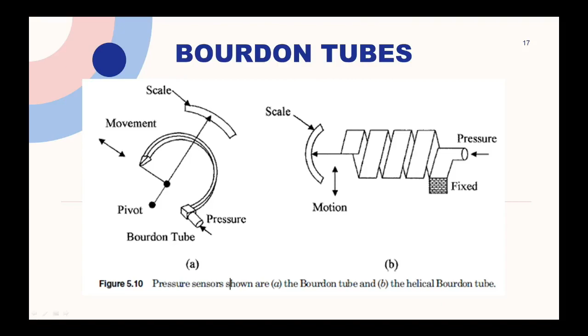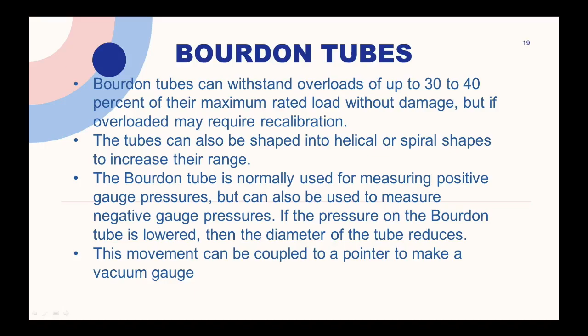Bourdon tubes can withstand overloads up to 30 to 40% of their maximum rated load without damage, but if overloaded, may require recalibration. The tubes can also be shaped into helical or spiral shapes to increase their range. The Bourdon tube is normally used for measuring positive gauge pressure, but can also be used to measure negative gauge pressures. If the pressure on the Bourdon tube is lowered, then the diameter of the tube reduces. This movement can be coupled to a pointer to make a vacuum gauge. So, Bourdon tubes can have a pressure range of up to 100,000 psi.